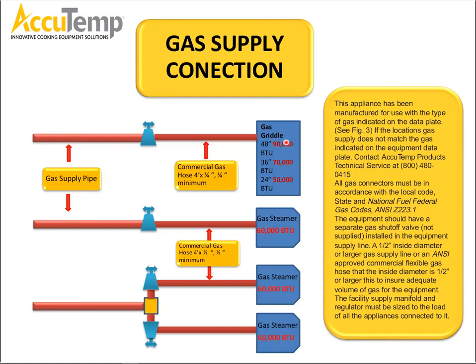Steamer, depending on the size, we've got the same. For a steamer, we could probably get away with a 1/2 inch. I think a 1/2 inch can support a little over 80,000. But once again, that's minimum. Minimum, yeah, it's fine, but let's bump it by 1/4 inch. So let's maybe run 1 inch into the griddle, and maybe 3/4 inch into the steamer, just in case, so we're 100% sure that we have that supply and the griddle doesn't drop out during normal operation.